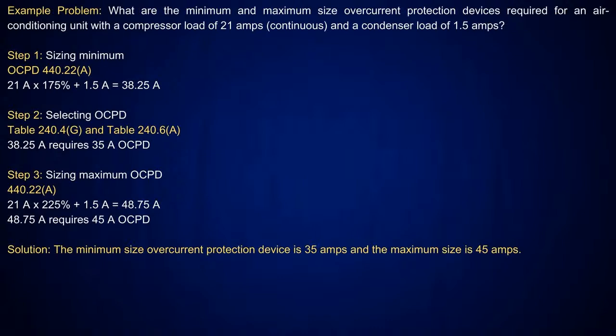Okay. Now I will tell you, in the 2023 cycle, I've already added another step here. I've added step 3 that will pick up 440.22(A) exception 1, and you'll be able to put a 40 amp there. Then I go down to the maximum size, which will be exception 2, that says I can take it at 225%, but I won't exceed the calculated value again. So I take the 21 amps at 225%, add that 1.5 amp condenser on there. That gives me 48.75 amps. The next size below that is 45 amps. So this calculation is actually changed in the 2023. I would have a 35, 40, and 45 amps set there. Okay? Right. Because you need to be aware of that.